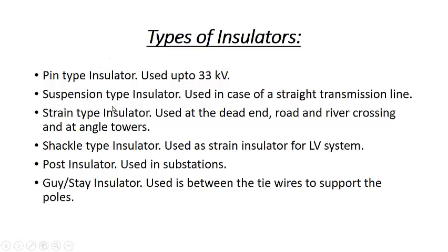Suspension insulators are actually made up of disc insulators which are suspended in case of a straight transmission line, where we don't have any bend in the transmission line. We can use the suspension type insulators, or we can say more than one disc insulator connected in series. We can say it is a string insulator. The other one is a strain type insulator. It is a similar insulator to that used in suspension insulator. Only thing is that its configuration will be different. The suspension type is usually connected vertically. The strain type is usually connected horizontally because of the strain of the line.